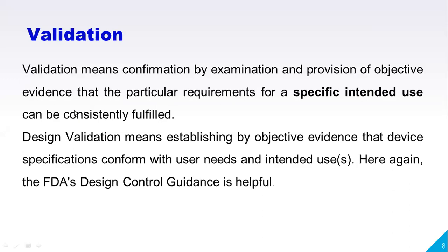Right. So then coming to the validation. Validation means confirmation by examination and provision of objective evidence that the particular requirements for a specific intended use can be consistently fulfilled. That means, as shown in the first diagram in the first image, according to the intended use, whether that medical device is manufactured or not.